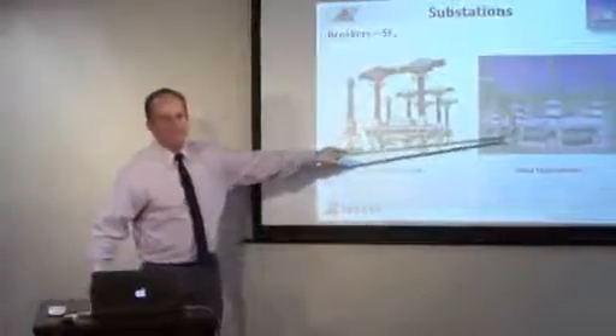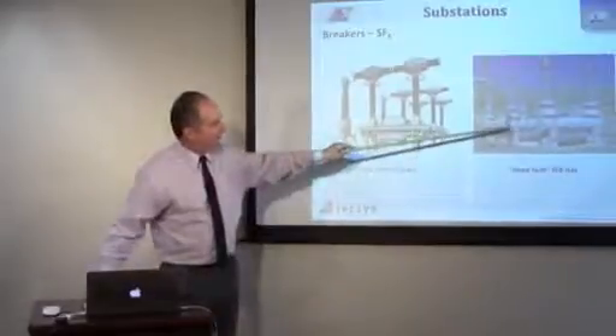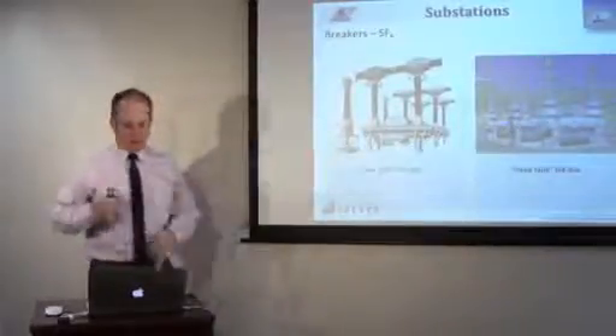Let's talk about the dead tank first. The dead tank, the circuit breaker contacts. You know, a circuit breaker is really designed so when the current is flowing through, let's say through here, okay, I've got contacts here. When I open up the contacts, there's going to be an arc, but it stops the current flow, turns off the lights, okay?